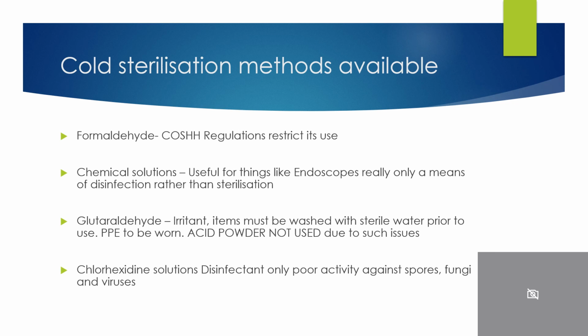We can use some cold sterilisation methods. In the past we used to use formaldehyde. This is now restricted via COSHH regulation, so this isn't something that we should be using. Chemical solutions, these are really useful for things such as endoscopes. Really is only a means of disinfection generally rather than sterilisation. Glutaraldehydes, these are irritants. Items must be washed with sterile water prior to use. PPE to be worn. They are an acidic powder, so again this isn't something that we commonly use in practice. We can also use chlorhexidine solutions. Generally this is disinfectant only because this has poor activity against spores, fungi and viruses.